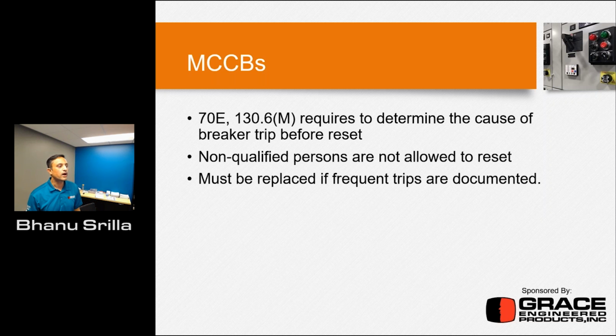Also, non-qualified persons are not allowed to reset the breaker. I'm not sure how many people really follow this in an industrial setting, because an operator can look at the tripped breaker and, because of production pressures, just think it's a switch and turn it on. That could be a huge risk for this person. The breaker must be replaced if frequent trips are documented. If you're seeing a regular pattern of the breaker tripping, or nuisance tripping, whether it's because of a fault or not, you need to take this breaker down and verify its functionality before you put it back, or replace it if it's doing that on a regular basis.